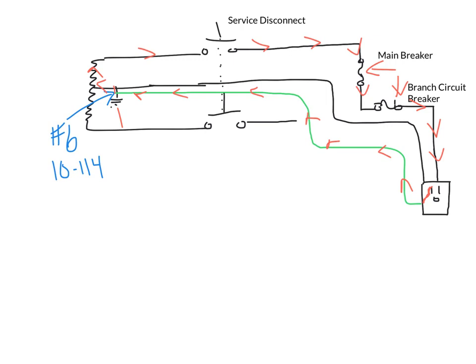You make sure that you remove paint underneath bonding lugs on any of the equipment that you're installing. Keep in mind that the value of these faults can be quite high. A basic formula for figuring out fault current is to take your current rating on the secondary of your transformer and divide it by the percent impedance of the transformer. So, for example, if the secondary current on this transformer was 100 amps and it was 2% impedance, our fault current would be 5,000 amps.